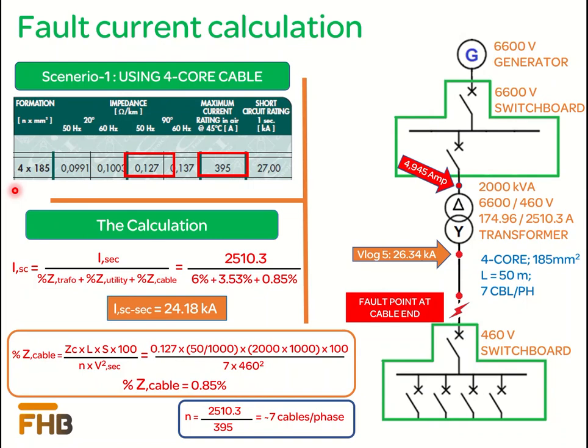Here is the first scenario where we have selected the 4-core 185 mm² cable for our calculation. To calculate the short circuit current, first we need to calculate the total short circuit impedance of the circuit during a short circuit condition.